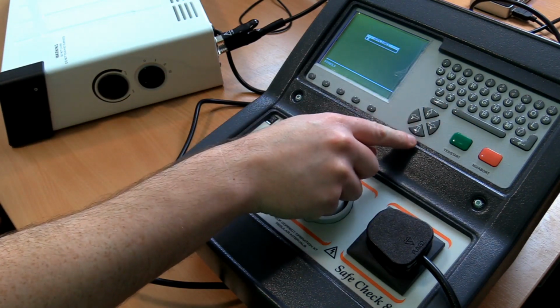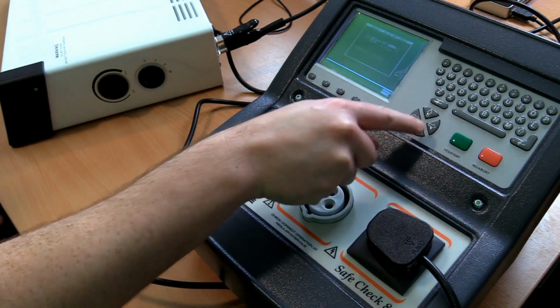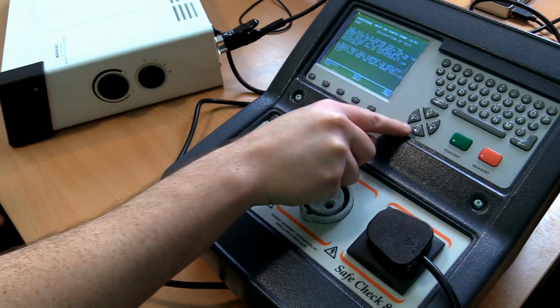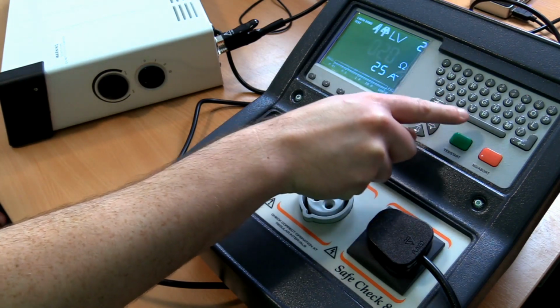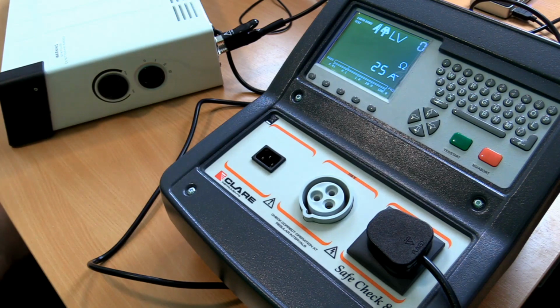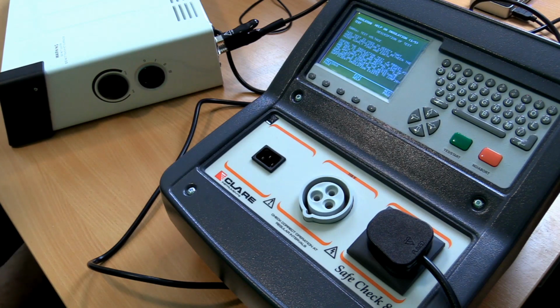So we're going to go new test, put in any old appliance number, choose our insulation resistance test, start off with an earth bond test, make sure the earth's good. Excellent. And now moving on to the insulation resistance tests.